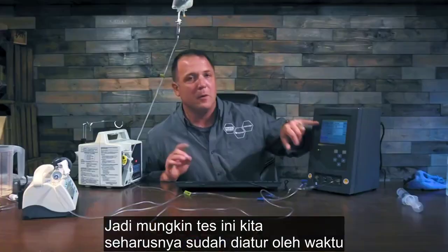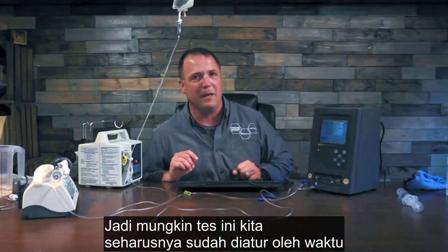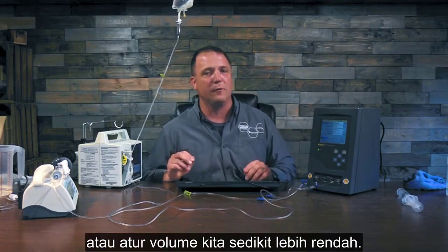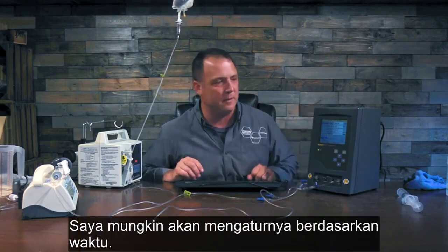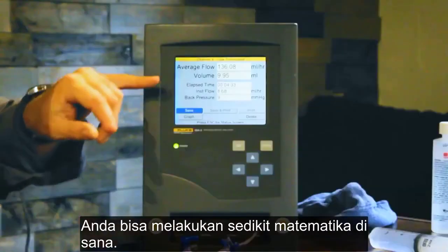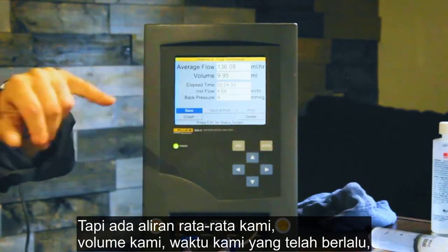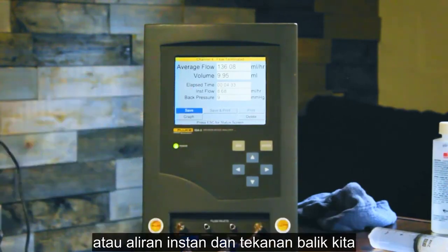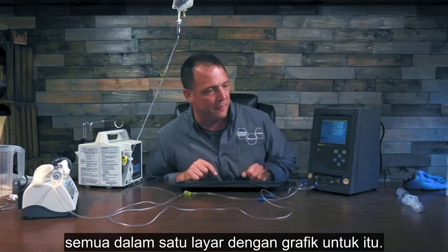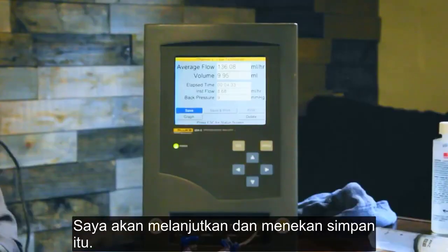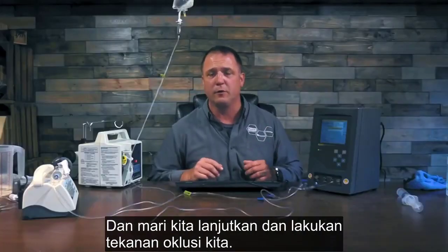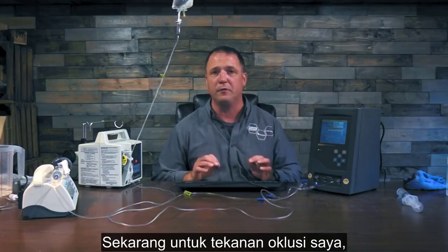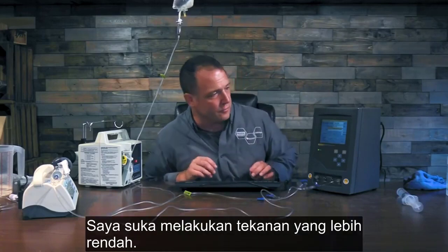So maybe this test we should have set up by time, or set our volume just a little bit lower. I would probably set that one up by time. You could do a little bit of math there. But there's our average flow, our volume, our elapsed time, our instant flow, and our back pressure. All on one screen with a graph for it. I'm going to go ahead and hit save on that. And let's go ahead and do our occlusion pressures. Now for my occlusion pressures, I like to do lower pressures.